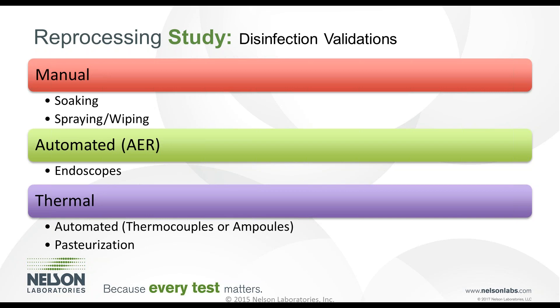Automated AERs are usually used for endoscopes — similar to a washer disinfector, specifically designed for endoscopes where you place the scope in and it runs through a disinfection cycle. Thermal disinfection utilizes a washer disinfector, and this is where the big difference lies between the U.S. and European markets. For thermal disinfection in the U.S., you're looking for a log reduction requirement, whereas in the EU market they use what's called an A-0 value.